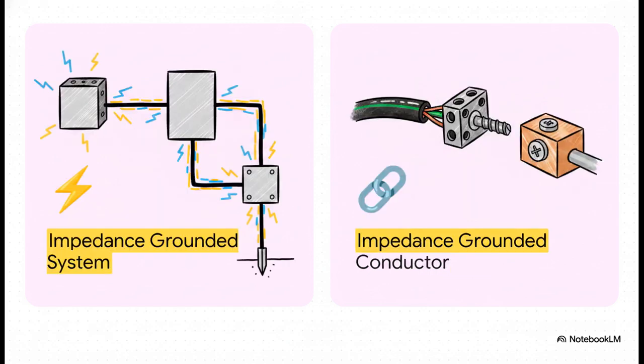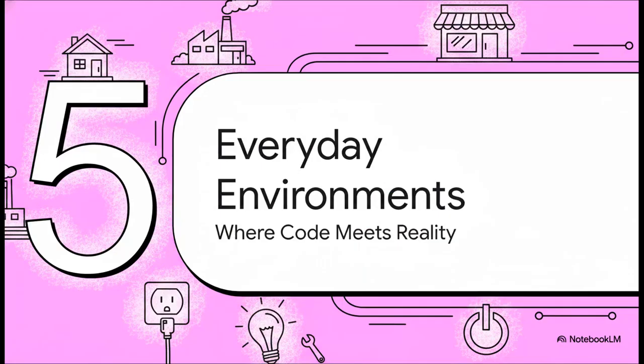The code also tackled impedance grounding, adding some much-needed clarity by splitting it into two distinct definitions. First, you have the impedance grounded system. That's the overall electrical system where the neutral is grounded through a designed impedance to intentionally reduce fault current. Conversely, the impedance grounded conductor is just the specific piece of wire connecting that neutral point to the impedance device. Before this update, folks out in the field were constantly confusing this specific wire with the system as a whole. Now, zero ambiguity.